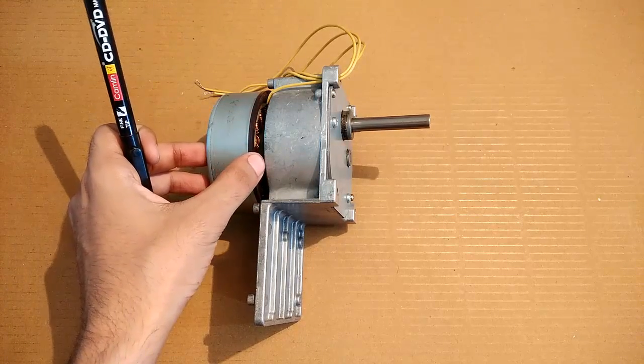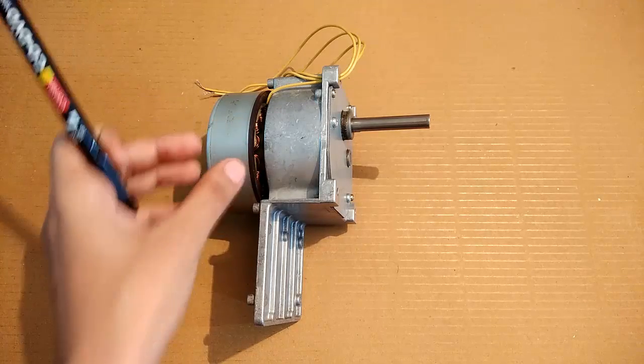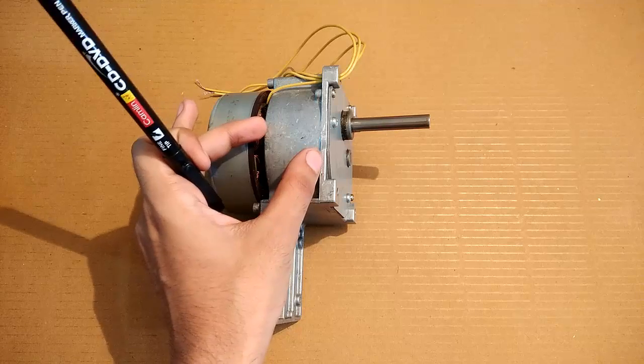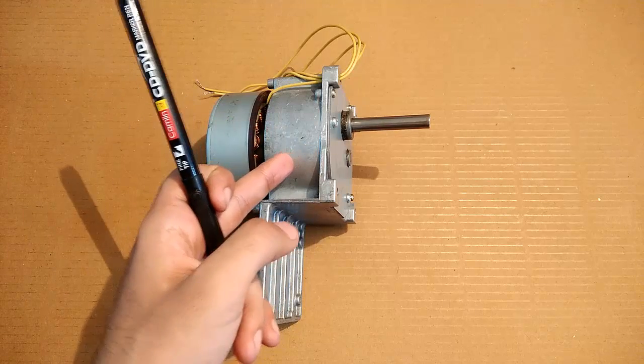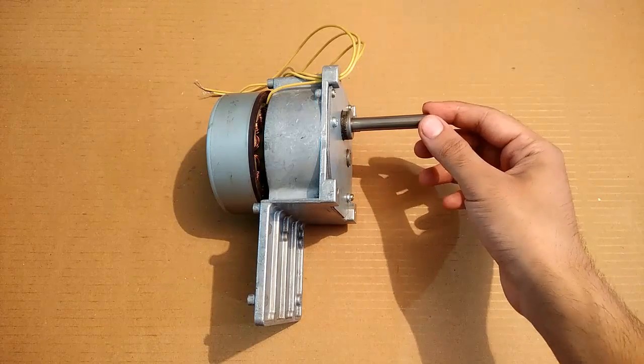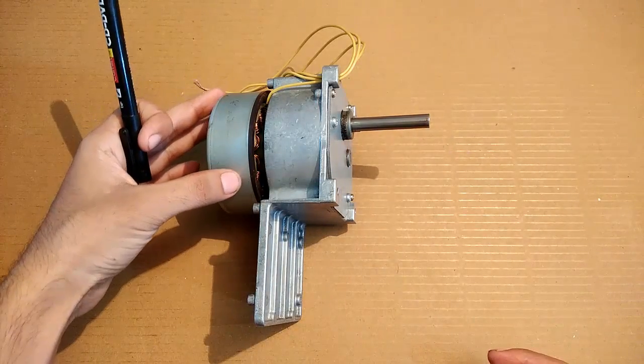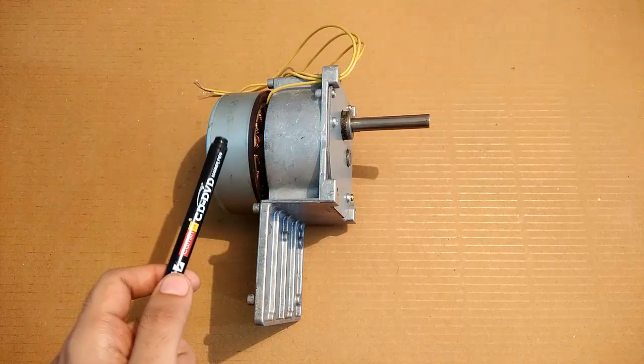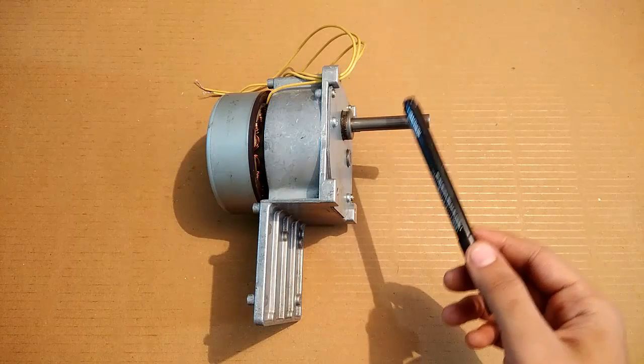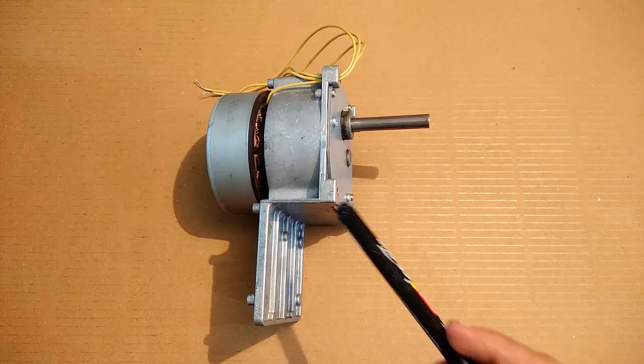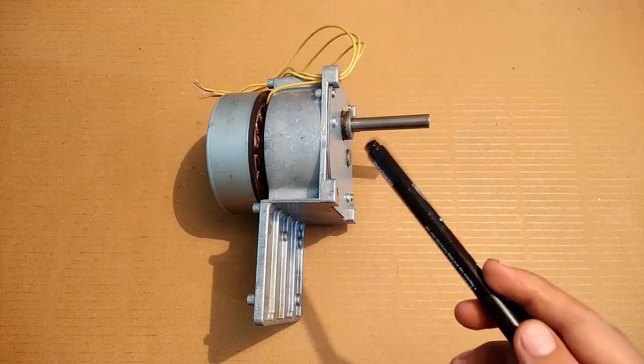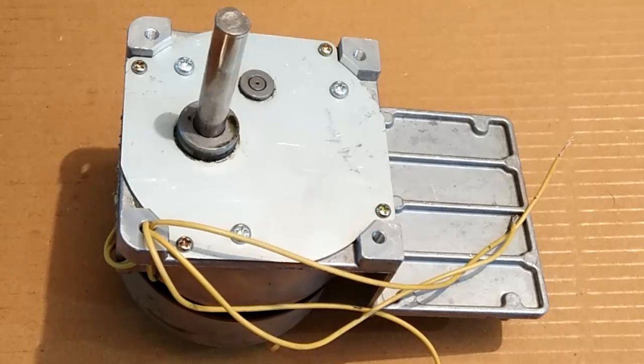This gearbox ratio is 10 to 1, which means if I rotate this shaft one time, then this generator will rotate 10 times in return. So this generator is rated at 1800 RPM, meaning the shaft RPM gets to be 180 RPM. The output voltage of this generator is 24 volts for 3-phase AC, and the current rating is 15 amperes.